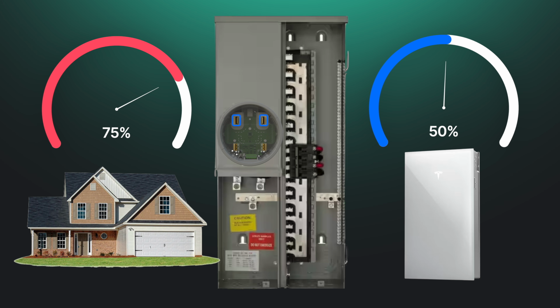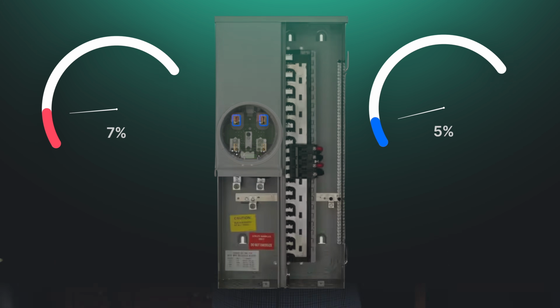Using our Powerwall 3 example again, without PCS, a standard 200 amp panel cannot accommodate a 60 amp breaker under the traditional 120% rule calculations. With PCS, the system is effectively saying, I know this bus bar is only rated for 200 amps, and I will continuously monitor it to make sure it never exceeds that rating.